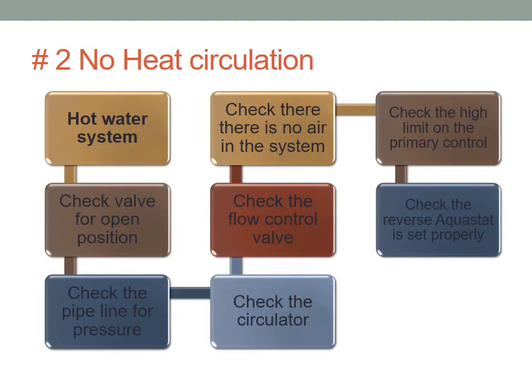Okay, we have heat, there is fire, the burner is working okay, but there is no heat distribution. So now we go outside the burner. First, if we have a hot water system, you want to check that the valves are open, those are the zoning valves.